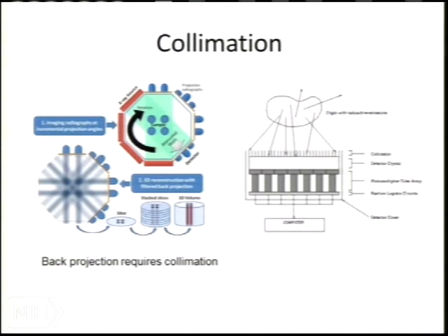But there is this problem that when you inject something that's a single photon emitter into a patient, there are emissions that go on in every direction possible. Sort of a cloud of gamma rays come out in all directions. So how do you possibly make an image out of that? Well, to do that, what you really need to do is to force some of these gamma rays through a channel, so at least you have some idea where they're coming from, and that's called a collimator.